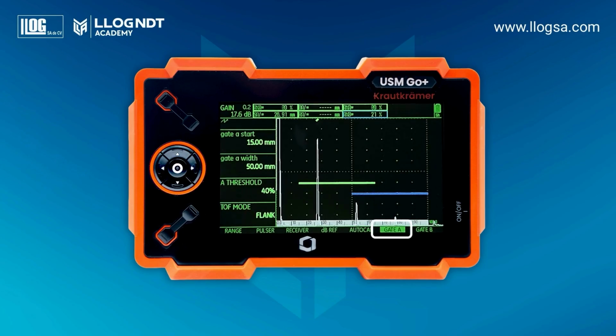The 6th and 7th groups are used for Gate A and Gate B settings. Each group allows setting the start, width, and height of the gate. In flank mode, the maximum amplitude within the gate is measured, along with the distance or time of flight from the first intersection between the echo and the gate. In peak mode, amplitude and distance are measured at the point of maximum amplitude inside the gate. Finally, note that these functions also apply to gate B.